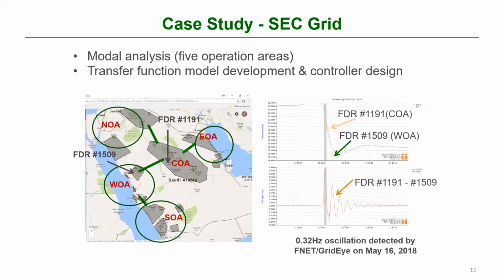And similarly, we have a monitoring system installed in Saudi, and this is the work we do with EPRI to look at their system. They also have this oscillation between the East and West, and that not only occupies the line in terms of not being able to transfer other power, but the power is just being bounced back and forth. But they also have a stability issue. Basically, if the oscillation grows and they have to trip the line, which is really between major load and major generation, that's crippling half of the country's infrastructure.